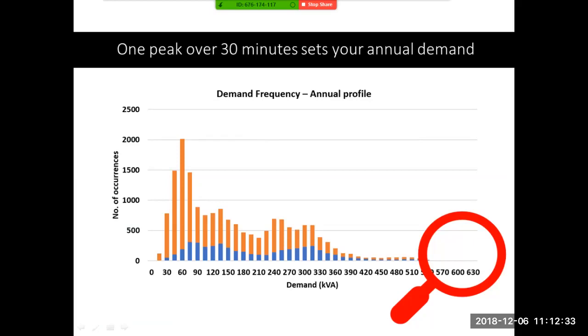Now this graph here is really interesting, and I see this time and time again. This is a demand frequency graph. It tells us your actual demand in kVA and how many times this occurs. What we can tell from this is that for this winery, on average, they use 60 kVA. That's their most common energy use. This would probably be their standby time. Now, we can see a peak here that's probably one refrigeration system kicking in and then a second refrigeration kicking in during this time.